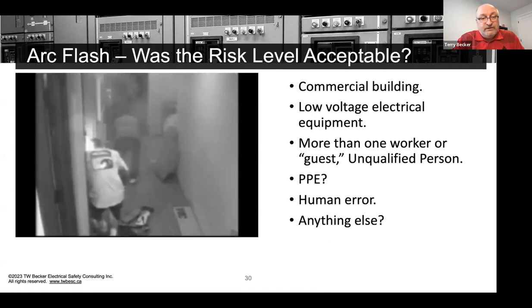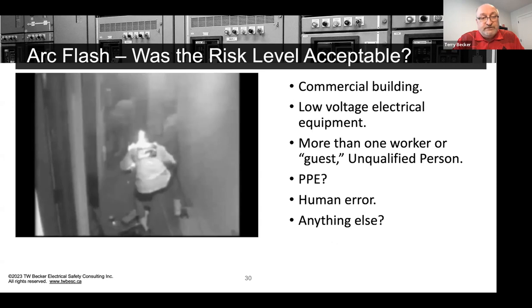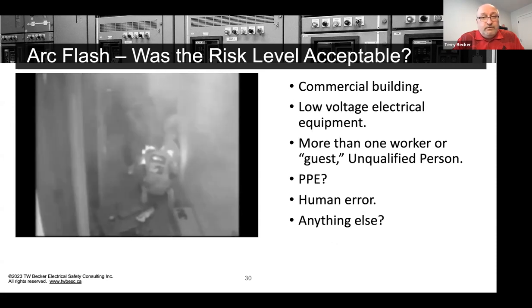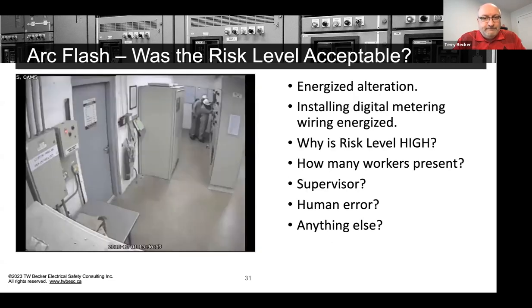So he puts a glove on the ground, which is interesting because it's actually a rubber insulating glove. There's the guest. So when we do arc flash or shock risk work, there are no guests. There are no people there that shouldn't be there that are unqualified or unprotected. So there was no electrical hazard identification. The strange thing is it looks like he put a rubber insulating glove down on the floor, but the primary individual, the worker, didn't have any arc flash PPE on.